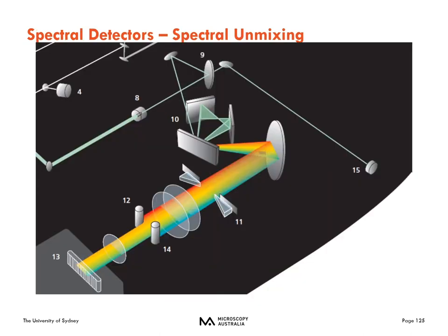There are also spectral detectors where you have a 32-detector array that splits the light spectrally, allowing you to capture a full emission spectrum. This can be really nice especially if you want to do spectral unmixing — if you have two fluorophores that are very close together and want to ensure optimal separation, you can use a spectral detector and then use mathematical algorithms to be certain things are spectrally unmixed.